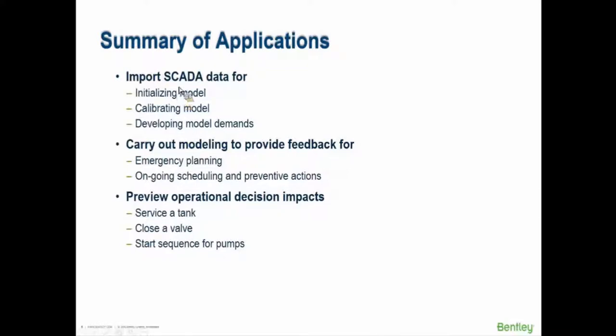The good uses in operations include emergency planning, scheduling preventive actions, and planning flushing using the model. You can take a tank out of service for painting and model what's going to happen first. You can see what happens if you close a valve or change a valve setting, or if you turn a pump on at a different time. You can see what's going to happen several hours from now before you do it. There's a lot of value in having the model available to support operator decision making.